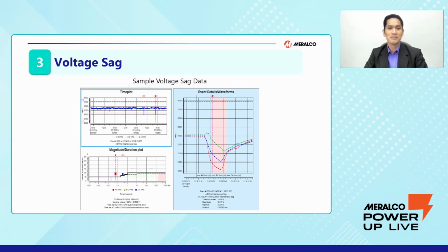So here is an example of some voltage sag data. From the upper left, from the time plot, that is the RMS voltage. This one is for 34.5 kV nominal service voltage. The upper and the lower broken red lines are the allowable 10% of the 34.5 kV, that is 110% for the top and 90% from below. There is some time in this one that there is a sag, and when we check the event in the details waveform, we could see that the red line, that is phase A, went below the 90% of the nominal for 58 milliseconds.